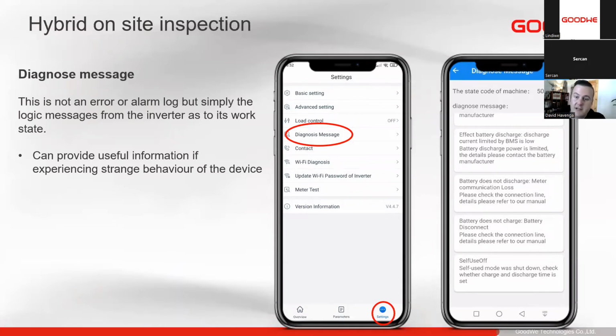Next, we have diagnose message. Diagnose message is very often confused with a fault message or an alarm. It is not an alarm or an error or a fault. It is simply the logic messages of the inverter. We use that for diagnosis when very strange conditions are happening, to see maybe the BMS is telling the inverter to charge the battery now, and then the inverter will be charging the battery when it's not supposed to.